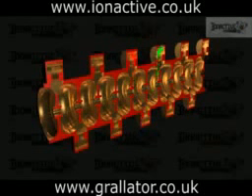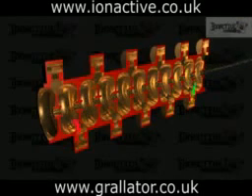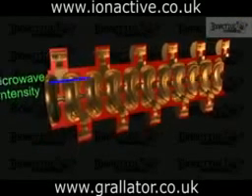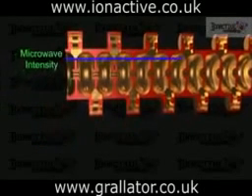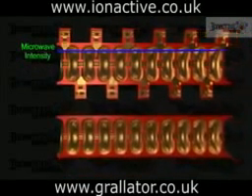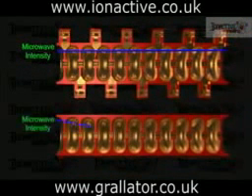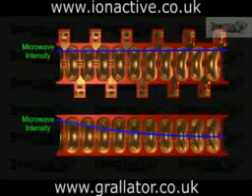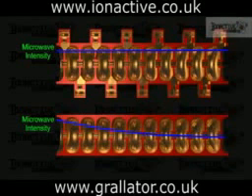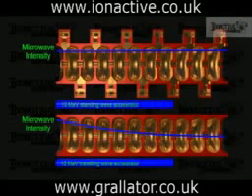The microwaves pass through all the cavities while the electrons pass only through the central ones. In this design, the microwave intensity is uniform down the length of the accelerator waveguide, whereas in the travelling wave design it is attenuated during its travel. Because of this, a standing wave accelerator gives a higher acceleration per unit length and so can produce an accelerator that is shorter than the equivalent travelling wave design for a given energy gain.